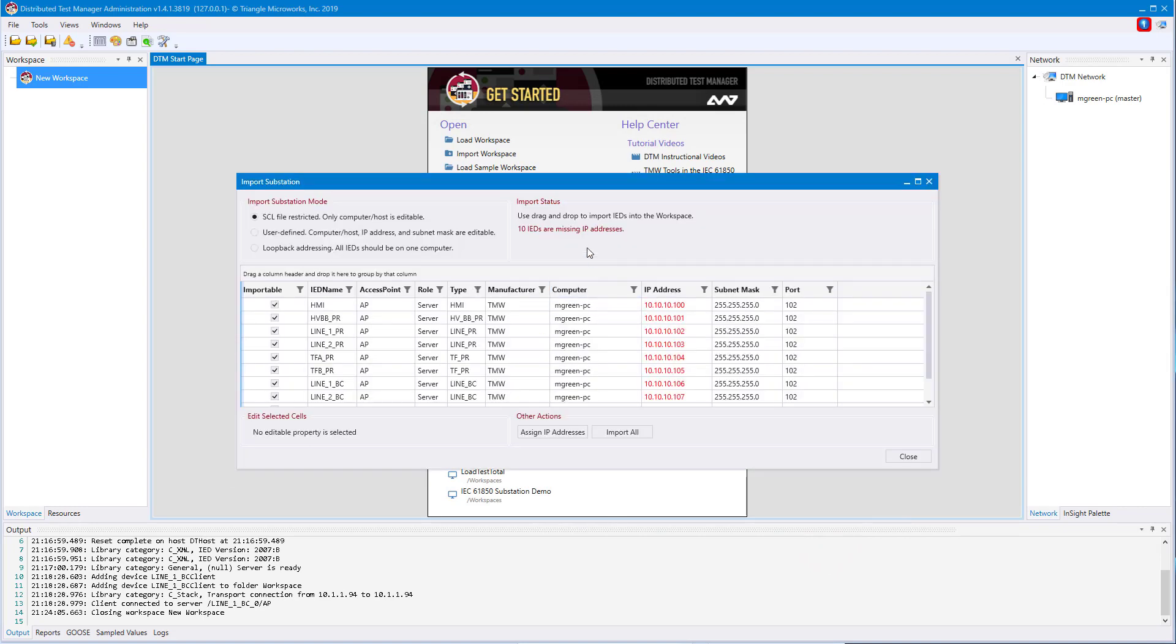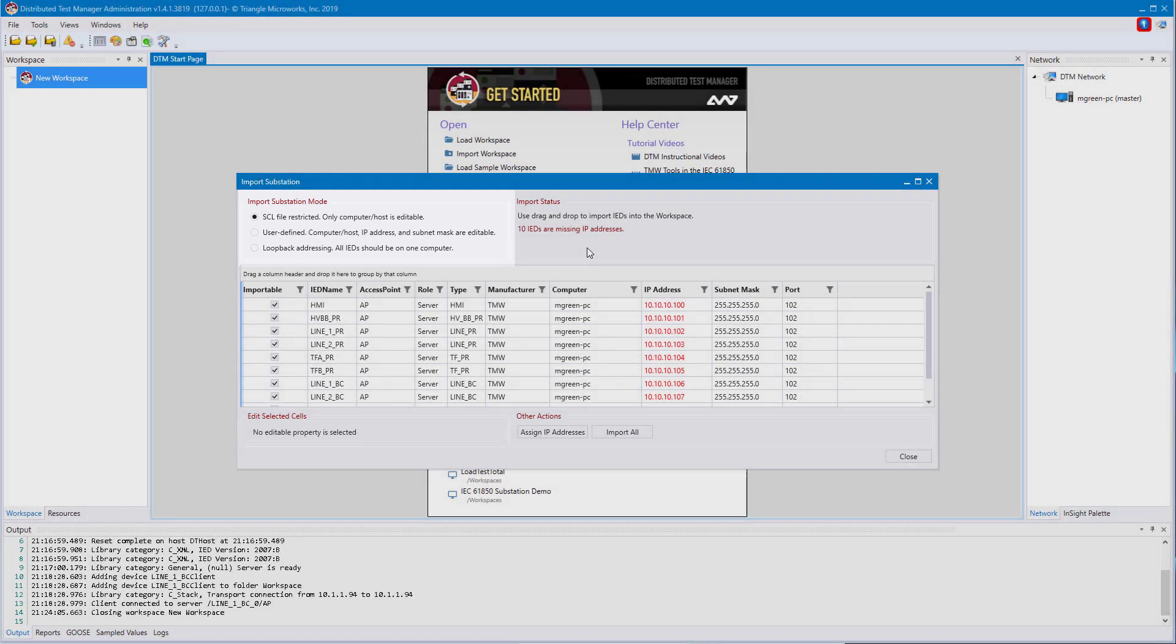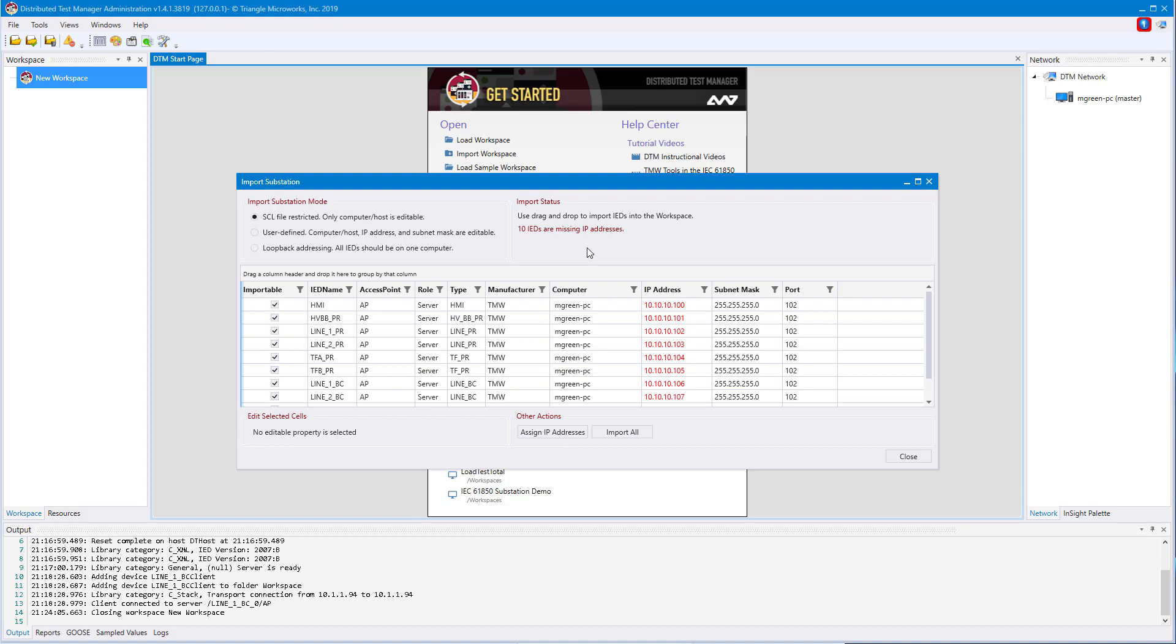This is our import substation tool. There are three modes you can run in this. The first mode is SCL file restrict. In this mode, you are tied to exactly what the SCD file defines. This includes IP address, subnet masks, and port numbers. This mode is used to verify everything that you have is properly configured.